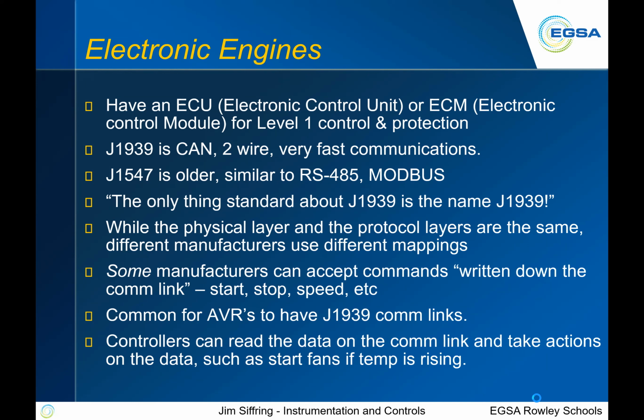So some manufacturers can accept commands that are written to the comm link. Some of them can't. It's all common now to have J1939 that talks, or you're talking over J1939, to voltage regulators, other devices that are out there: engine controllers, genset controllers, voltage regulators. There's other things that we can talk on that J1939 loop. And then there's other things that the J1939 data can do. It can take that data and use it to say start fans if temperature's rising, or open louvers, or do other things in a system.